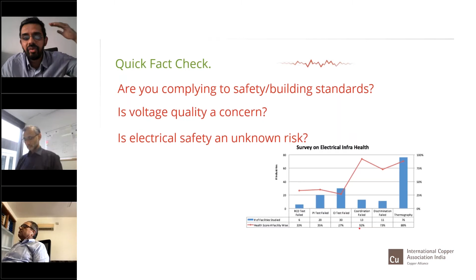This reveals phenomenal gaps that are missed during the installation phase by the last mile contractors and their workforce, which are driven more by experience rather than professional learning or skilling. As you can see in this graph, we have been doing tests on hundreds of different kinds of equipment like breakers, RCDs, transformers, and conductors, and we find a high number of failures in terms of test parameters. Almost 92% of facilities have a missed coordination between the breakers, all the way from high voltage to low voltage.